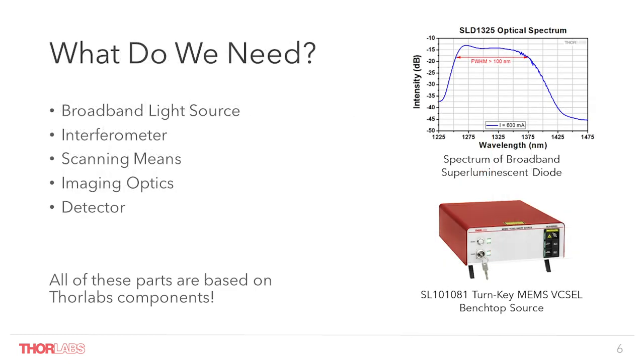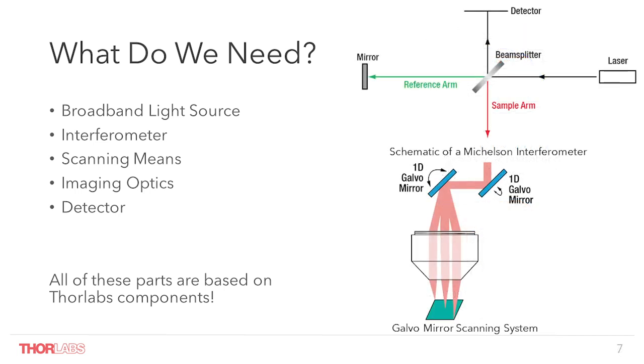What do we need for an OCT system to work? In principle, not too much. We need a light source — ideally one that is spectrally very broadband. Here on the top right you can see the spectrum of a superluminescent diode, and on the bottom a MEMS VCSEL benchtop laser as we use them in our OCT systems. Then we need an interferometer, so we have to divide the light into a sample beam and a reference beam. How this is done differs for different approaches — in some cases we use common path probes with bulk optics and free-space beams for both interferometer arms, and in other approaches the reference can be fully within a fiber.